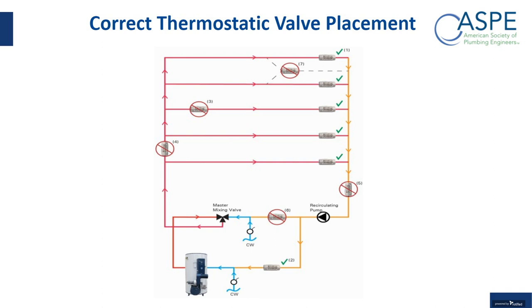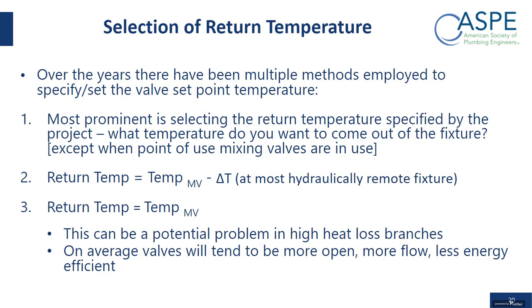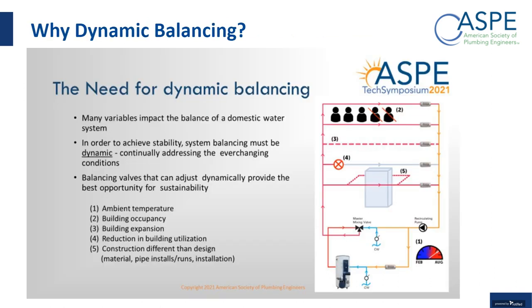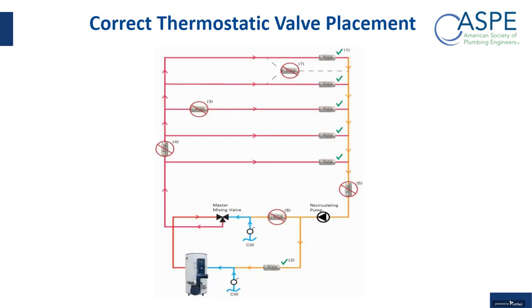So this is an important slide from the standpoint of first-time users with thermostatic balancing valves. I used to always say early on, people would say, where do I put these thermostatic balancing valves? And I'd say, put them in the same location you put your manual balancing valves. But I stopped short there, and then I started to realize after seeing some issues that engineers would typically, in a lot of cases, use manual balancing valves in other locations, not just the typical location at the end of a branch or riser before the return.